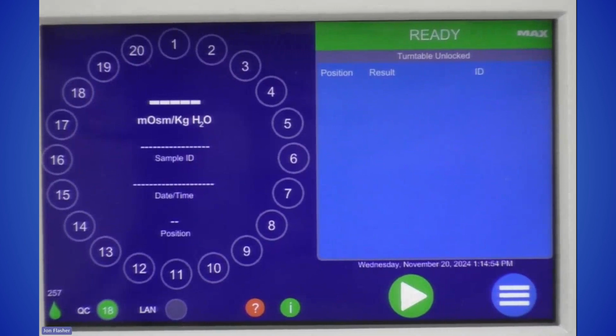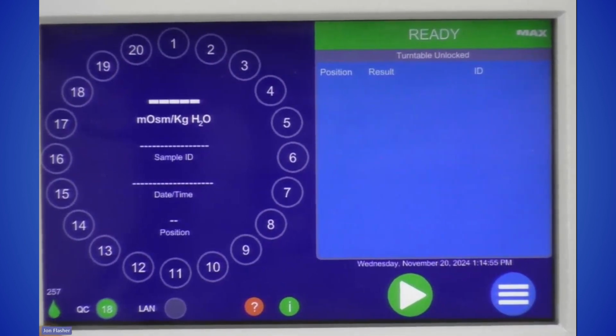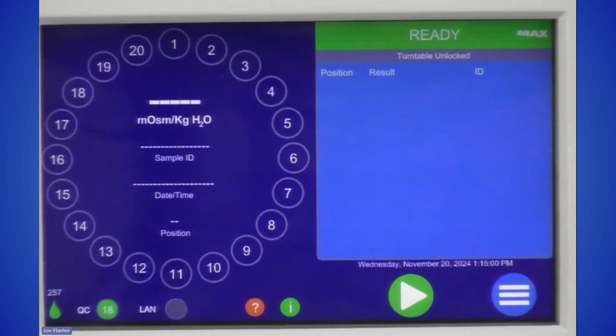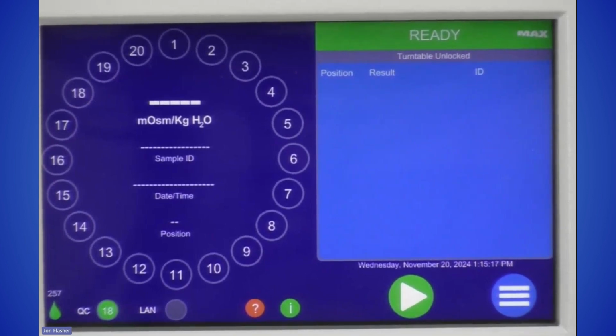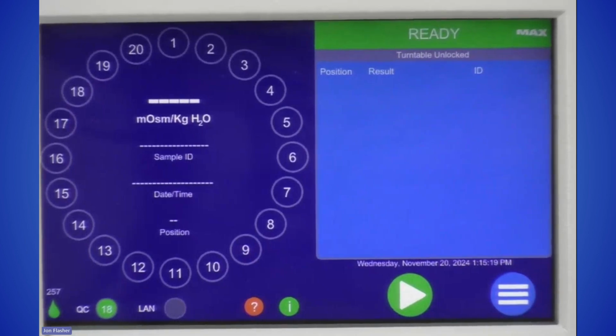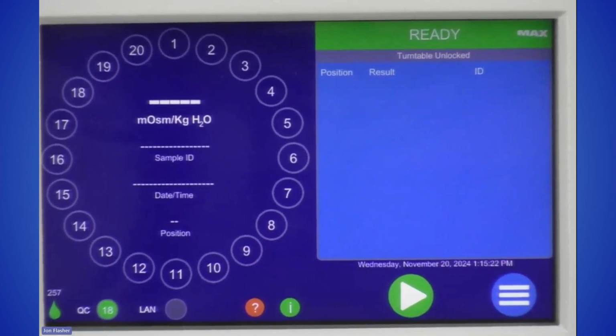So what else is helpful to know about this home screen? This little green teardrop-looking thing is our counter for the number of tests that we have left before performing the required 500 test maintenance. As I mentioned before with the Max 500 kit, every 500 tests you have to go in and perform a maintenance where you change the system fluid, change the peristaltic tubing, and perform an enzymatic cleaning. This will count down from when that event happens, and the little green teardrop will change to yellow when you're getting a little close, and red when you're very close to needing to perform the 500 test maintenance.